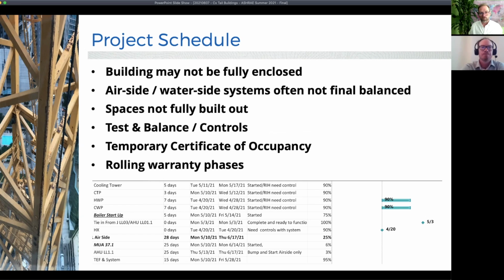On the air pressurization side and testing of those units like the exhaust fans, things like not having registers and diffusers and grills in place can cause issues with your test and looking at flow. So we see a lot of test and balance happens before everything's kind of a finished product like that, especially in multifamily residential where they're trying to get people in the building while you're still building it. It causes a lot of strain and access to the units to make sure that the local damper or local exhaust fan are on. In variable systems it's critical, and making sure that you have the correct percentage of those is a very important thing.